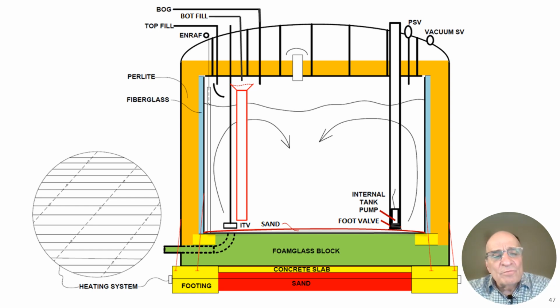Where do you measure your temperatures on the LNG underneath the tank? Well, you have other conduits that go this way, and you have thermocouples inside of here, or RTDs, resistance temperature devices, and these will tell you the temperature profile that's underneath your tank. Let's say you get a conduit that corrodes out or gets welded inside by arcing that occurs on your wiring that has now shorted out, and you can't get that wiring out. So let's say you lose this conduit, where you have to make up for that heat by adding additional heat to the adjacent conduits. And typically, they're not set up to only heat these conduits, so it's typical that your entire system has to be raised in temperature to make up for any losses of conduit.